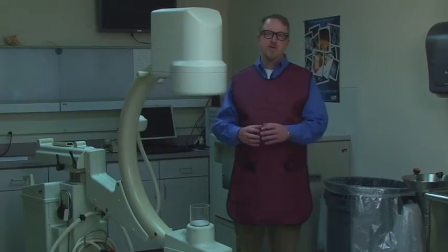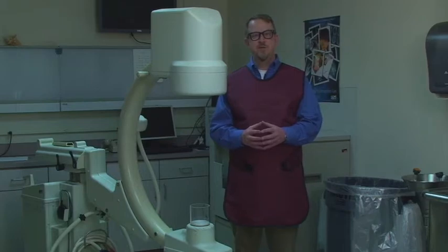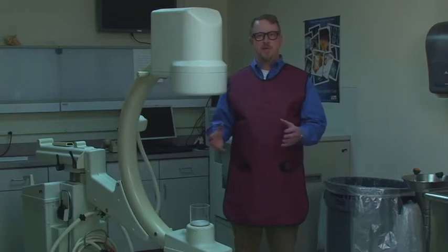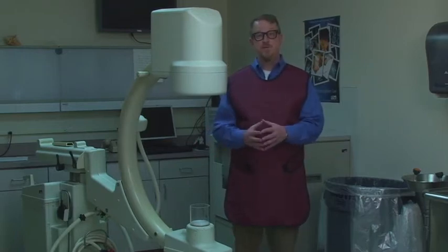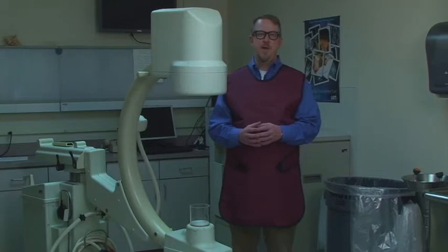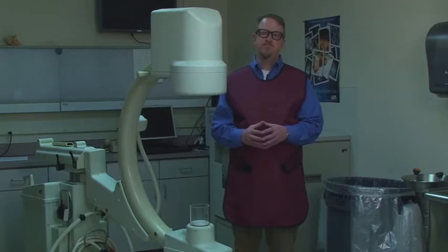This unit can be useful in the OR for both static and real-time imaging of fixation screws, pacemaker lead placement, or angiographic work. A C-arm can be draped for sterility and moved over and under the patient rather than moving the patient themselves. The challenge for the technologist is keeping track of the X-ray tube and therefore the direction of the primary beam, as its mobility means it can irradiate the patient and surrounding personnel from almost any direction.